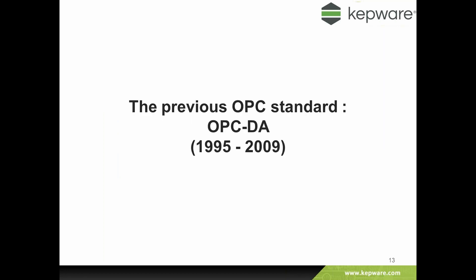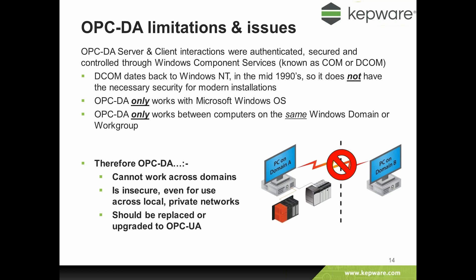Now that we've looked at how OPC clients and servers interact, I want to quickly look back at the old standard, OPC DA, which some people watching this webinar might be more familiar with. OPC DA existed between 1995 and 2009. It's still current in the Kep Server product, but it is a legacy standard which really shouldn't be used now. The OPC DA interface is based upon very old technologies — Windows DCOM — which is a security and authentication model originally launched in the mid-90s with Windows NT. Because it is so old, it really isn't secure, and we would not recommend anyone uses OPC DA these days.